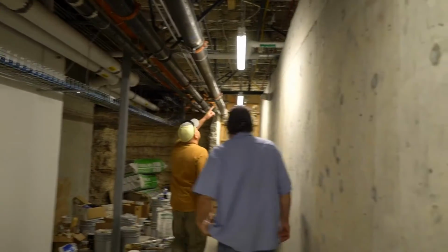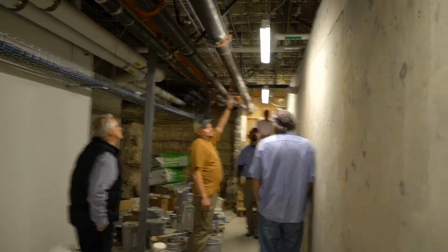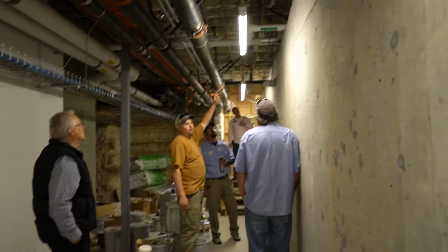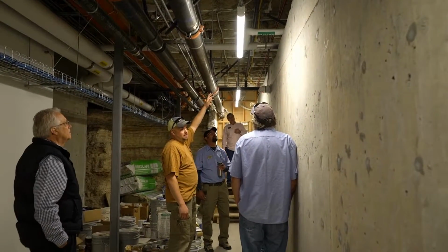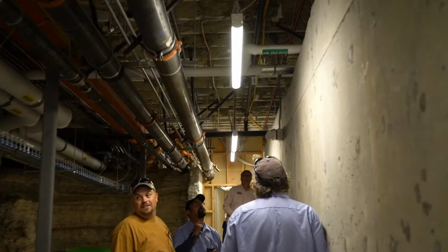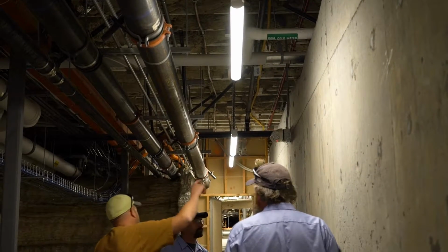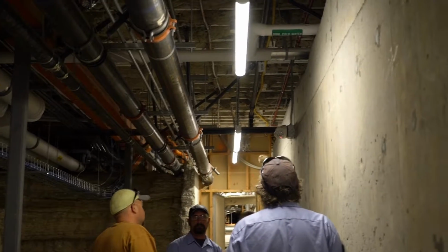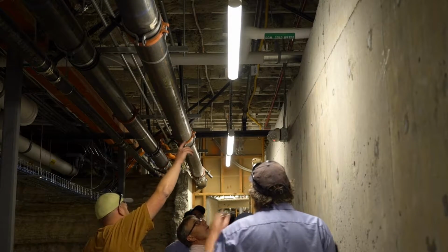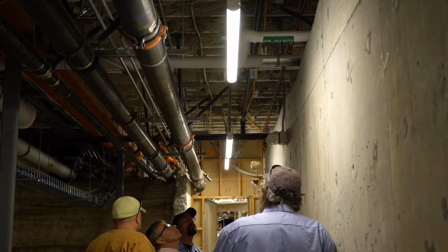This valve right here, you can see it's just barely cracked. That goes to your shell filling station. Otherwise, if it's fully open, it just sprays water everywhere. So I just wrote on there, throttling valve for the shell station, on that tag right there, that little 1/2-inch ball valve. The fancy water fountain, the bottle shell fill water fountain, the historic water fountain. If that valve's open, it just sprays water everywhere. So right there I got that set where it just has a nice steady stream. It just says throttle valve for shell station.